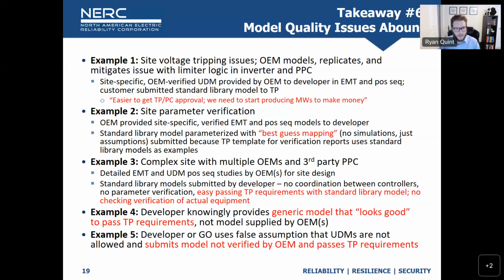Example 2: site-specific plant verification. The OEM provided a site-specific verified model in both EMT and positive sequence, but what was submitted to the TP was a standard library model parameterized with wave-your-hands, best-guess mapping—no simulations, just assumptions. That's because the template used to submit models uses a standard library model as the example. They may not say you can't supply a UDM, but since the template shows a standard library model, the developer assumes that's what's required. So they throw out the good model and submit a best-guess model instead, which is wrong and needs to be verified.